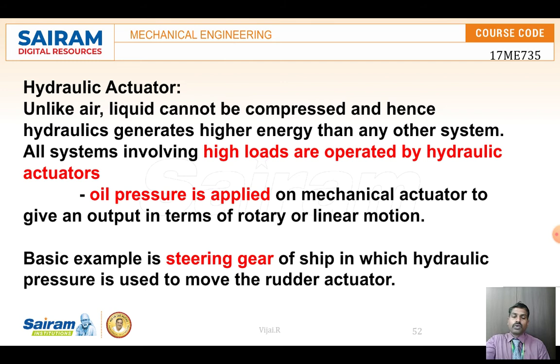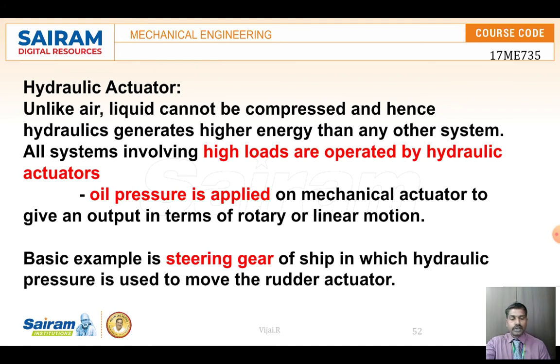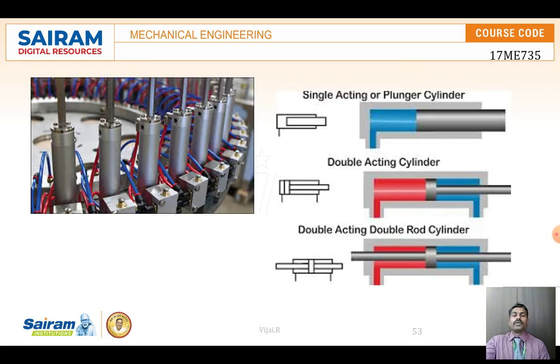Pneumatic and hydraulic actuators use a medium — hydraulic actuators use hydraulic oil for high-pressure or high-load applications. Hydraulics are used for very heavy load operations, such as hydraulic jacks for lifting heavy vehicles. Air can be easily compressed, but hydraulic oil cannot, making hydraulic actuators best for heavy loads. We can use single acting cylinders, double acting cylinders, and tandem cylinders, applying oil in one or both directions.